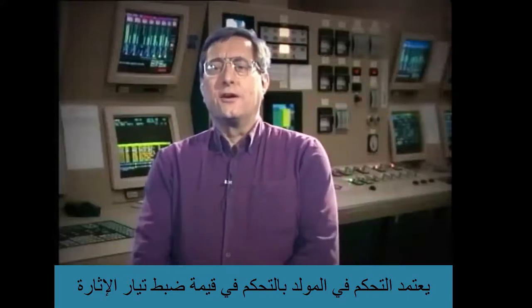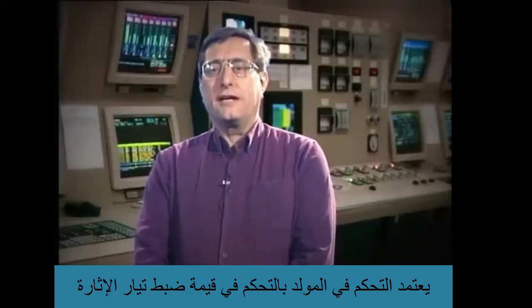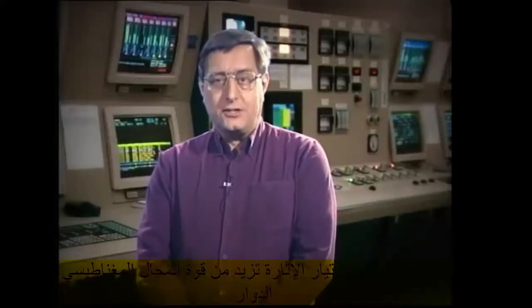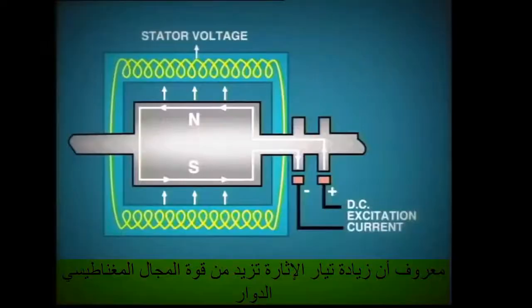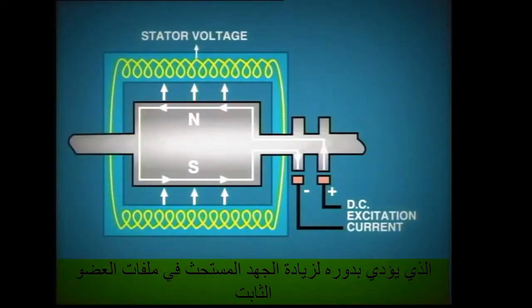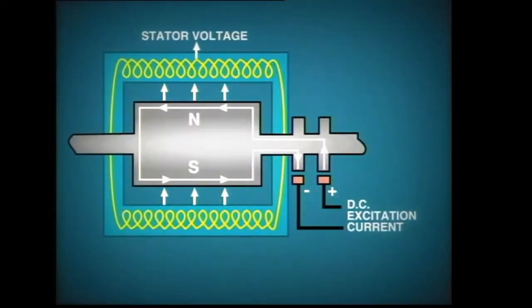Control of the generator output voltage is effected by adjusting the magnitude of excitation current. We already know that increasing excitation results in an increase in the strength of the rotating magnetic field. This in turn brings about an increase in the voltage which is induced into the stator conductors.